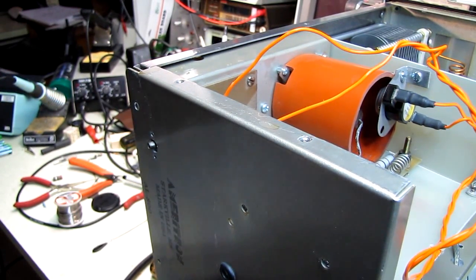After disconnecting the primaries and checking them out, I was showing a short to ground, or a 60 ohm path to ground, on one of the primary windings. There's two 120 volt windings that go in series for 240 volts. And that's when I noticed that the fan was in parallel, and I'd seen this on the schematic but it hadn't registered. The fan, a 120 volt fan, is in parallel with one of the primary windings, so that when you're running 220 volts it still sees 110 across one of the windings.